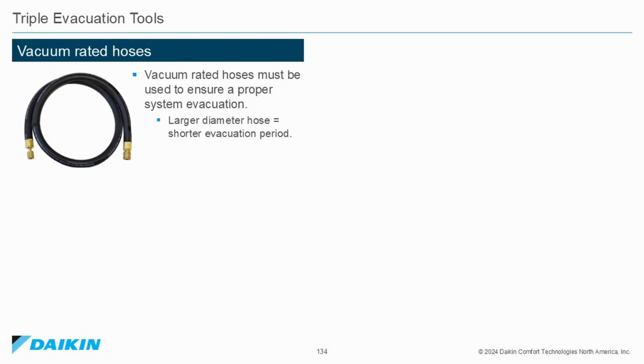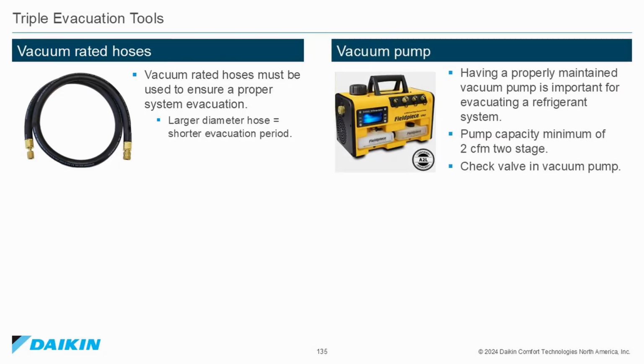Triple evacuation tools. Vacuum-rated hoses. Vacuum-rated hoses must be used to ensure a proper system vacuum. The red, yellow, and blue hoses that come with your gauges are typically not vacuum-rated. The larger diameter hose equals a shorter evacuation time. Vacuum pump. Having a properly maintained vacuum pump is important for evacuating a refrigerant system. Pump capacity should be a minimum of 2 CFM 2-stage. Check the valve in the vacuum pump.